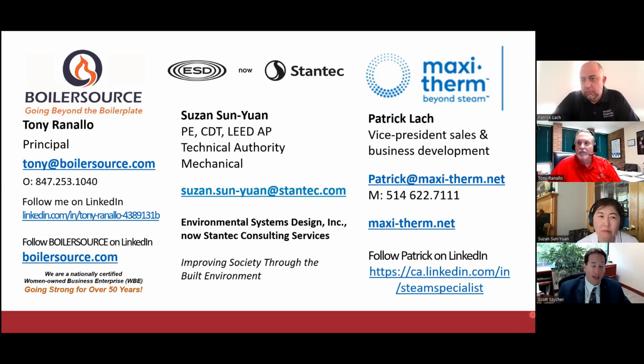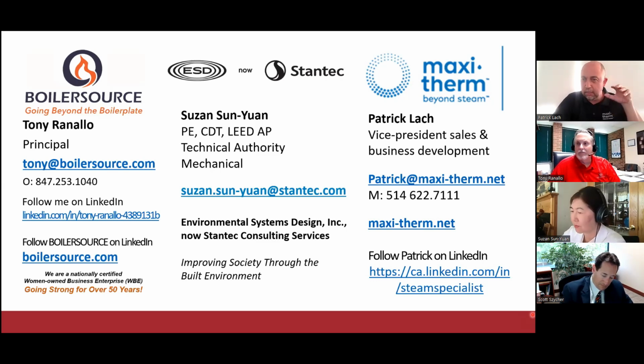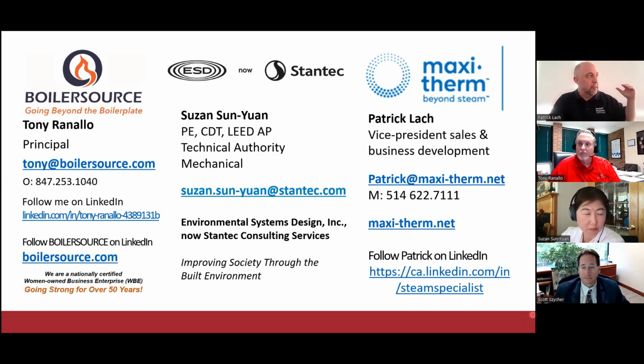Patrick, a big picture question for you. In your capacity as someone C-level at Maxi-Therm, are you seeing more or less demand for steam projects, both in the United States and Canada? That's an interesting question. What has changed over only the last 5 years is that we have more and more demand for big units. I know most of them are for mini or micro hot water district energy. They're going to bring steam in because it's easy to transport: 1 pound of steam travels 10,000 feet per minute, while 1 pound of water travels only 600 feet per minute. Hot water will then be fed to 5-6 buildings. So to answer your question, there's more and more demand for big units.